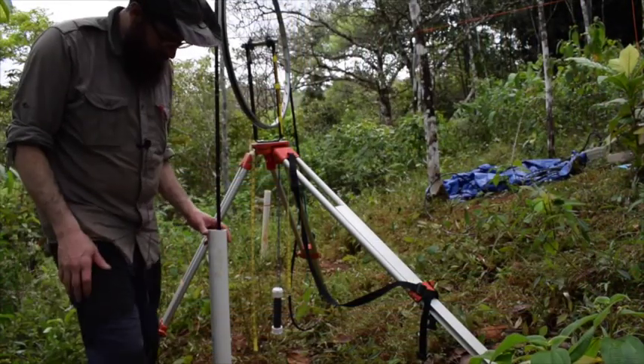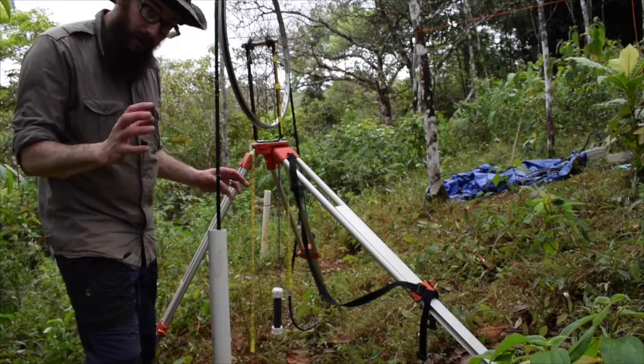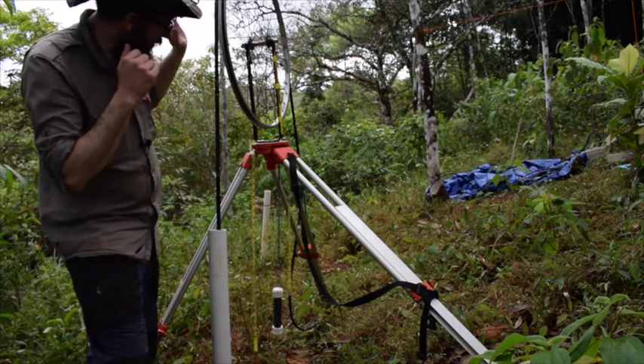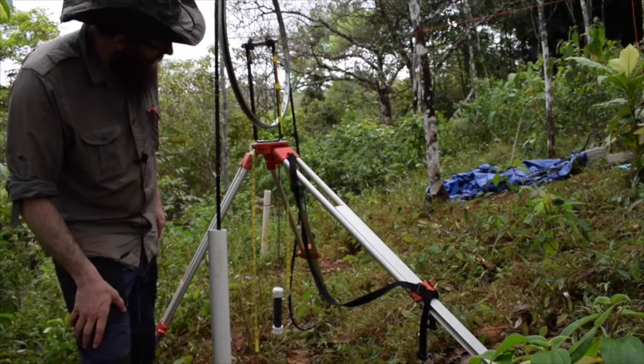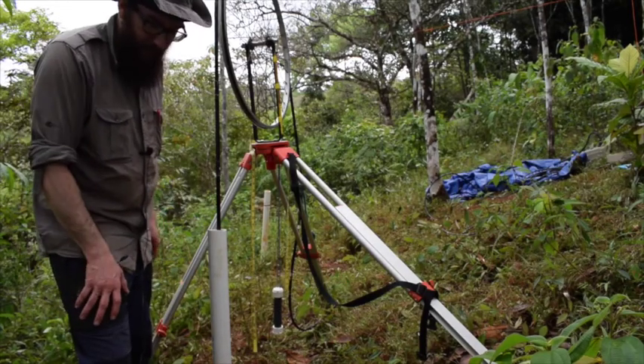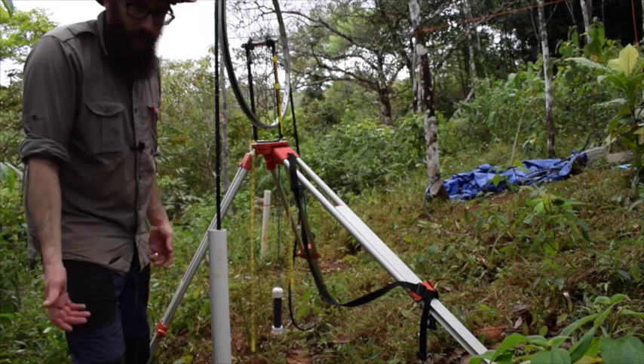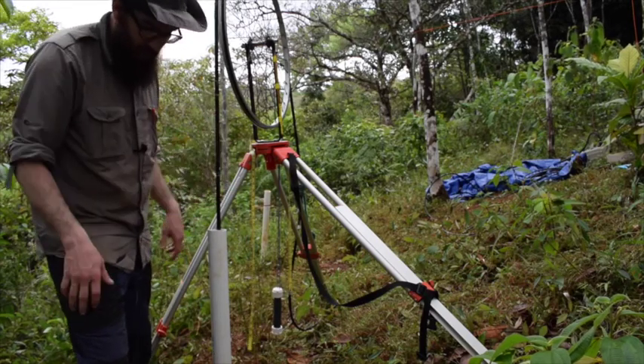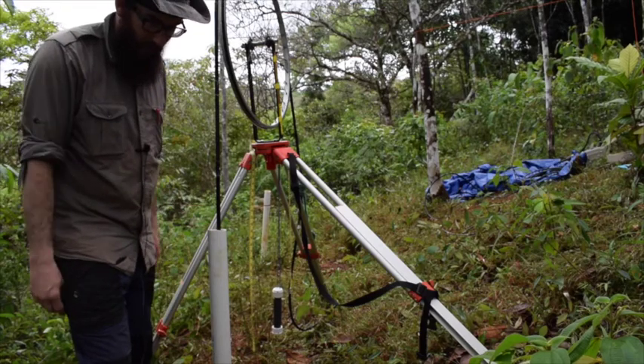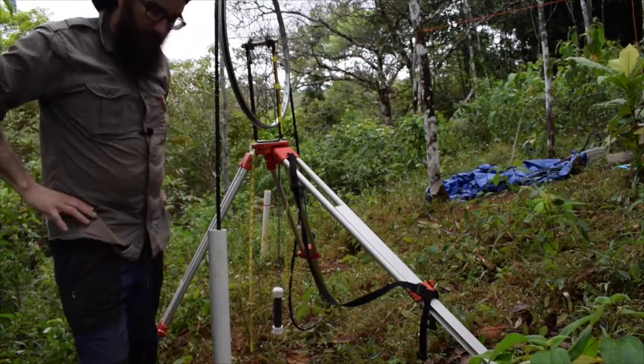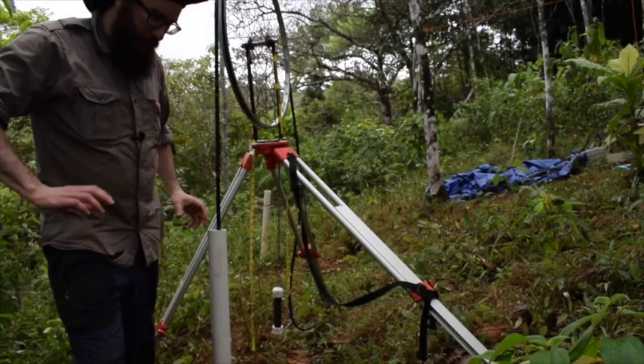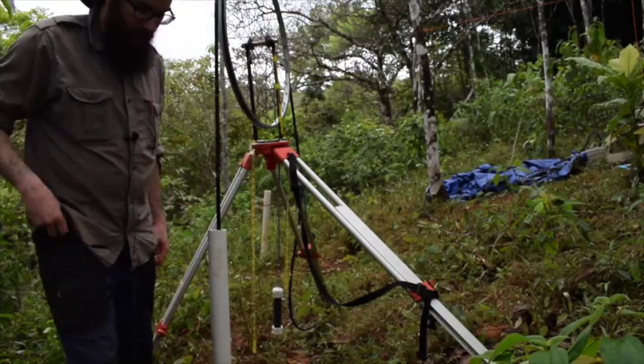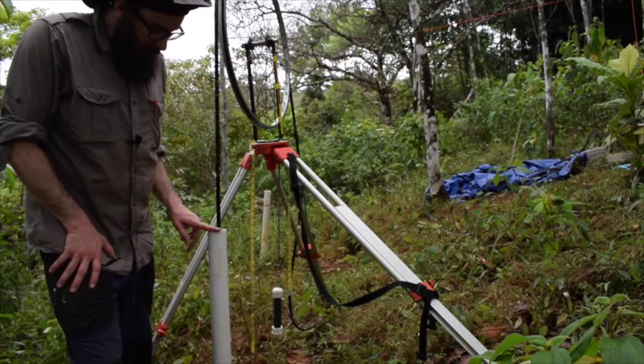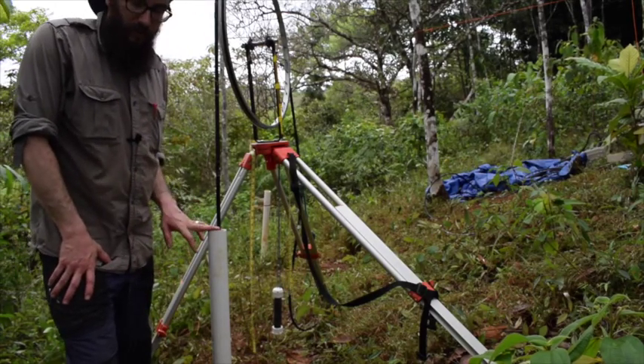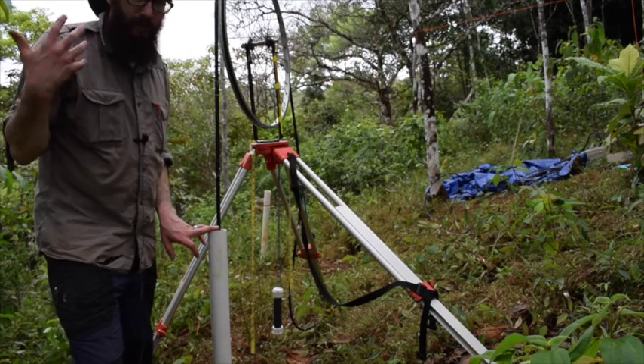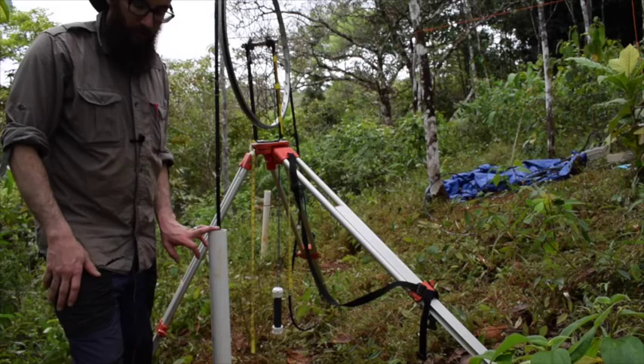A couple of minor notes here. One is the surface station: I'm keeping it about 5 meters away from the instrument, and that's an average good distance. If you can keep it farther away, that's fine. Of course, the total cable length is only 33 meters, so there will be a limit, depending on how deep your well is, to how far away you can keep it. That's just to reduce the potential for noise to interfere with the measurement. Probably the most typical source of noise on this measurement will be lightning, unless of course you're right near some infrastructure with power lines or cars or whatever like that.